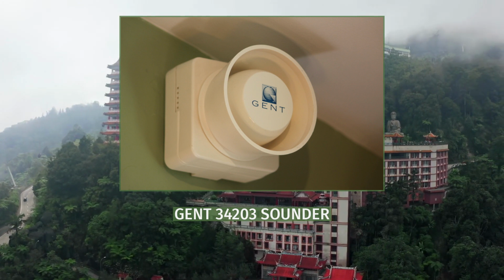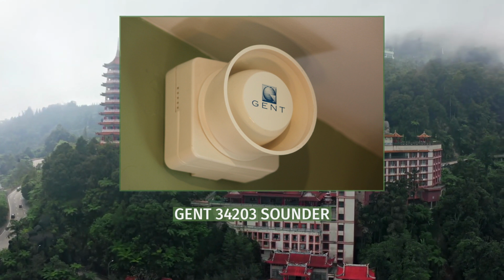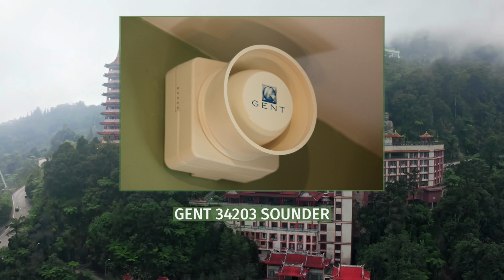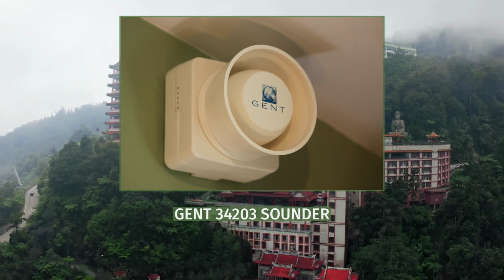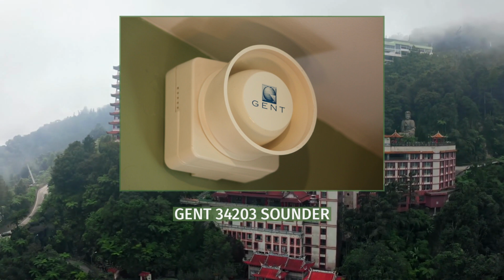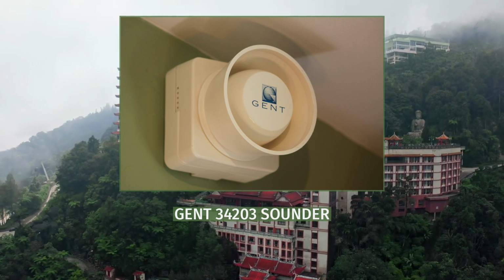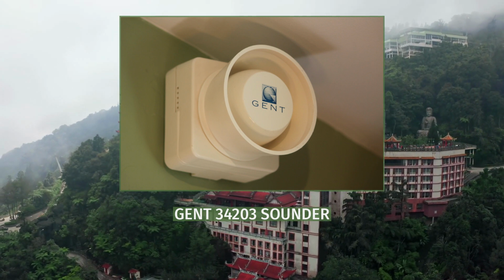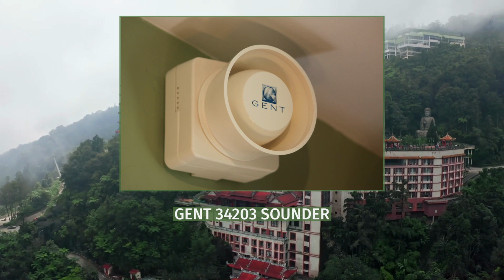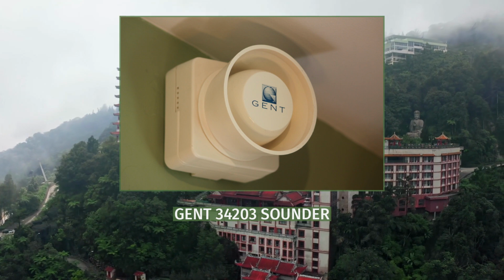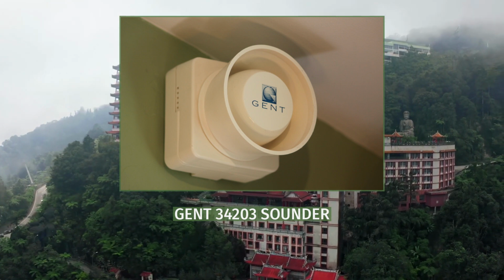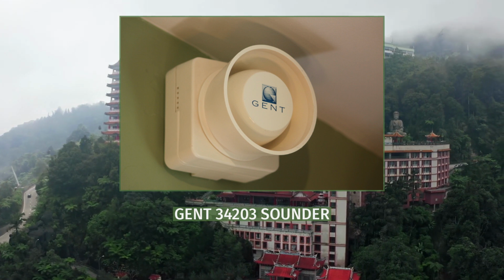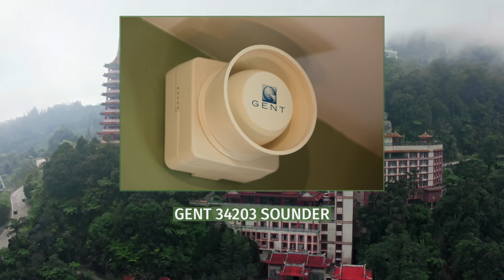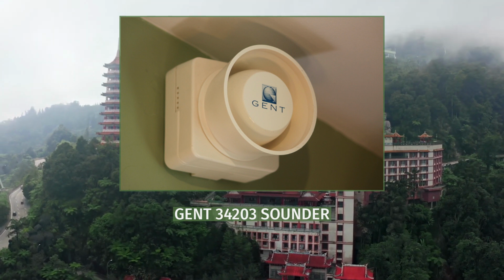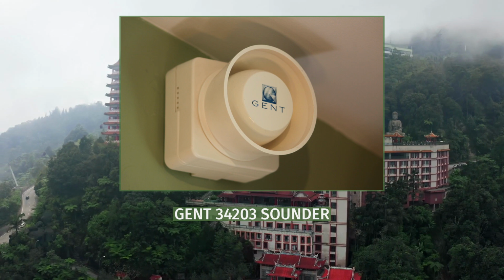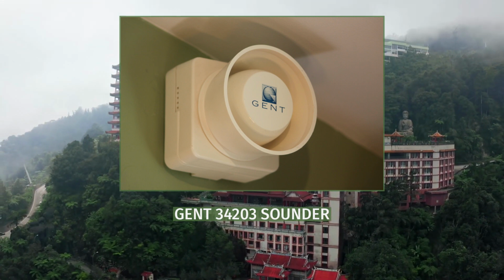In 2023, Gent introduced a new range of S-Quad detectors that are able to self-test both the heat and smoke elements of the detector. In applicable devices, the new S-Quad range uses real aerosol smoke to test the optical smoke sensor and ensure that the detector's entry points are not blocked. The detector temporarily disables itself to ensure that the testing process does not cause a system activation and a fire evacuation. These devices are also designed so that if another device, whether it is another S-Quad or a manual call point, is activated on the system, the self-test feature will be disabled and the fire system will return to normal functionality while other devices remain in an activated state.